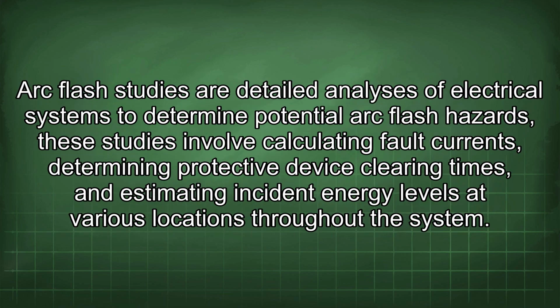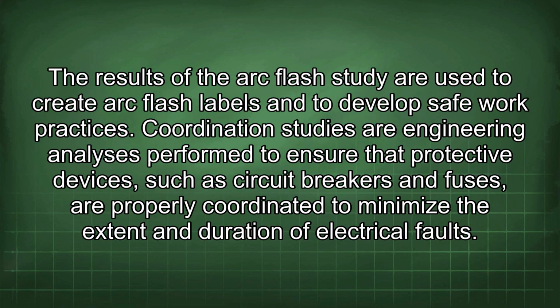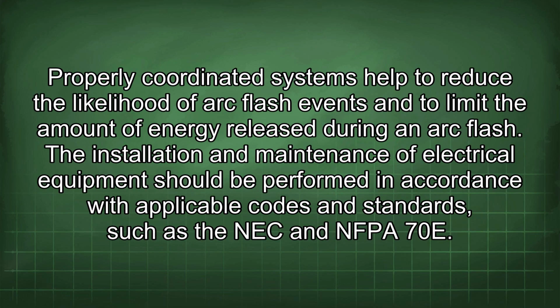Arc flash studies are detailed analyses of electrical systems to determine potential arc flash hazards. These studies involve calculating fault currents, determining protective device clearing times, and estimating incident energy levels at various locations throughout the system. The results of the arc flash study are used to create arc flash labels and to develop safe work practices. Coordination studies are engineering analyses performed to ensure that protective devices such as circuit breakers and fuses are properly coordinated to minimize the extent and duration of electrical faults.